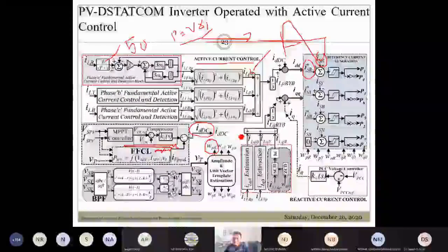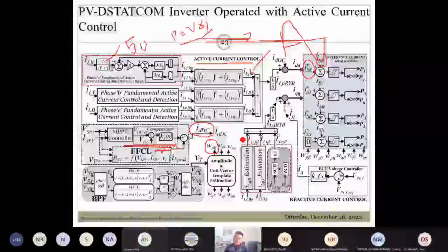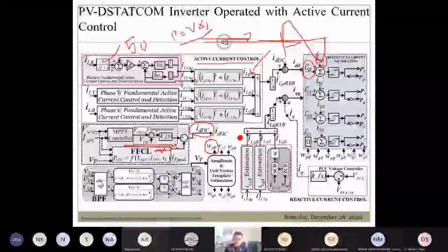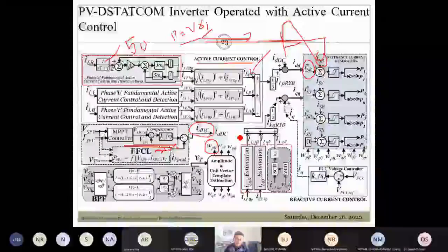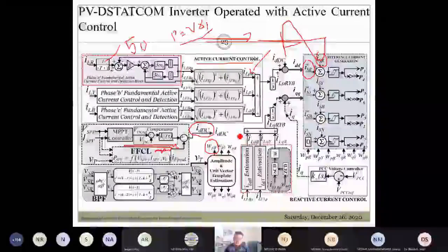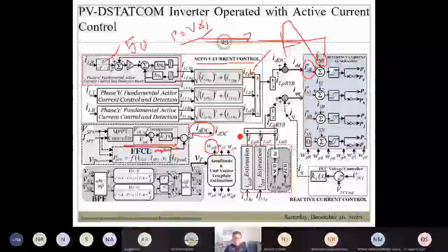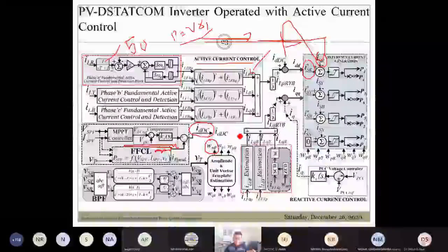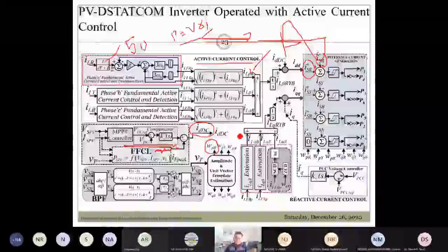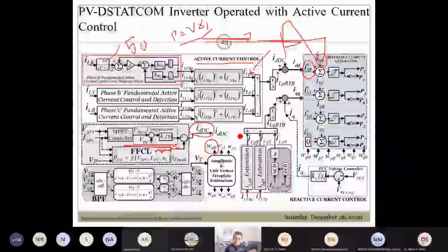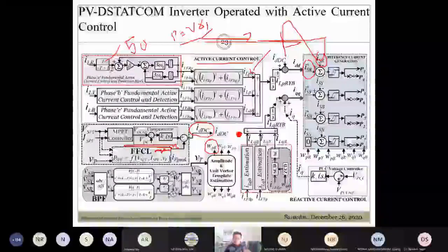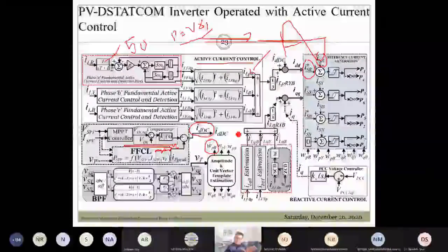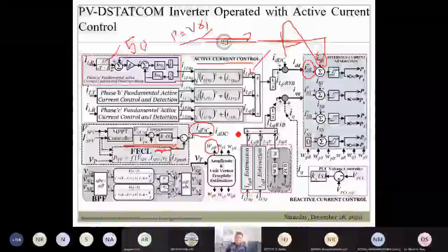But in case of the inverter, if you do not have the battery energy storage system and the load demand is increased, how will you control the frequency? You cannot ask the PV arrays to generate more power. So you have to have the battery energy storage system. You can ask it to provide the additional power during the sudden transition in the load, and this is how the frequency can be maintained well within the acceptable threshold of plus or minus 0.5.